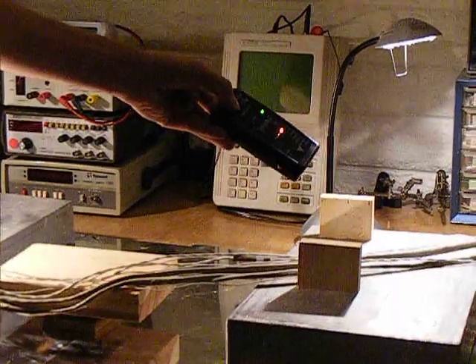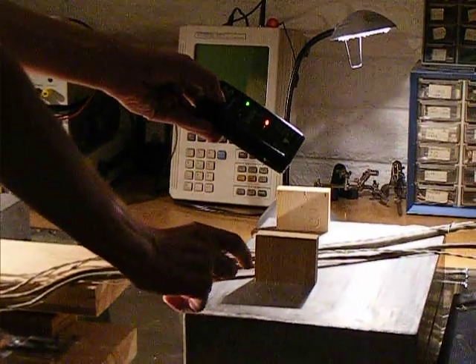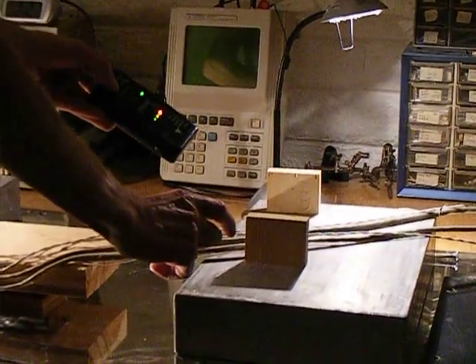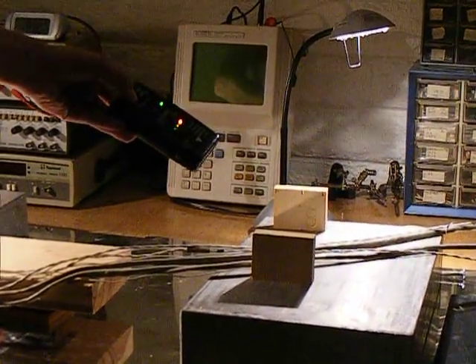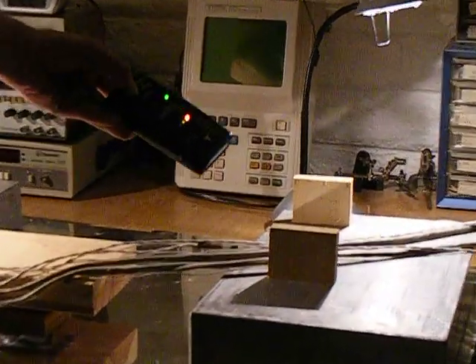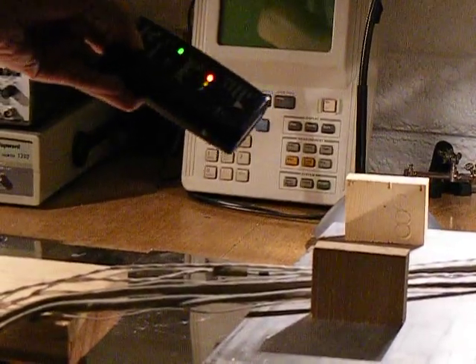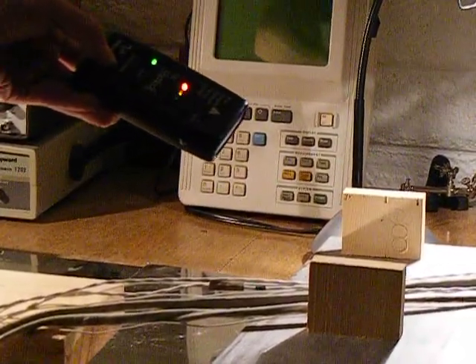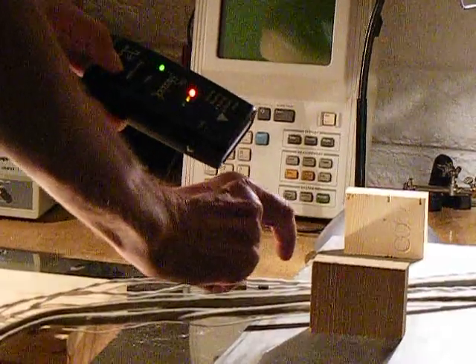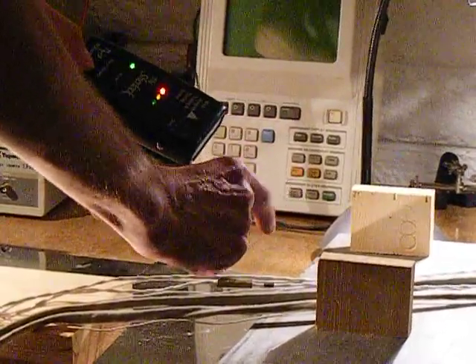So as we approach this area, we find there's our signal, and then it starts to diminish. So right where it starts to diminish, we go either side of that. There it's strong. There it's not strong. It's actually gone. There's our signal. So our short is right here.